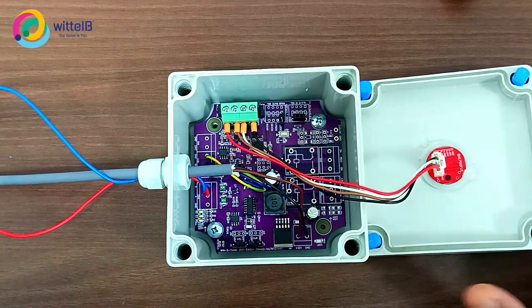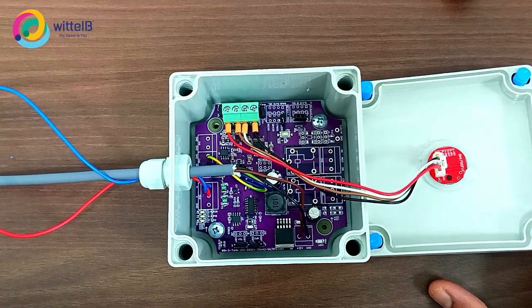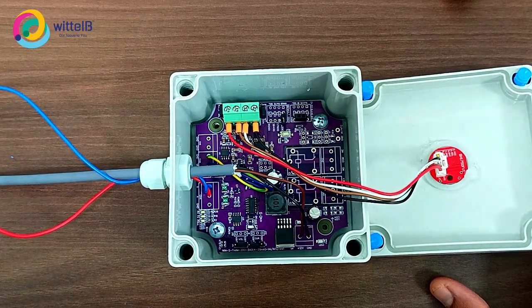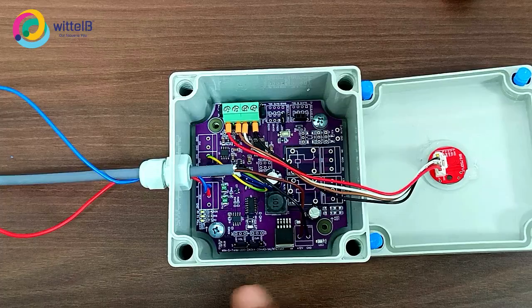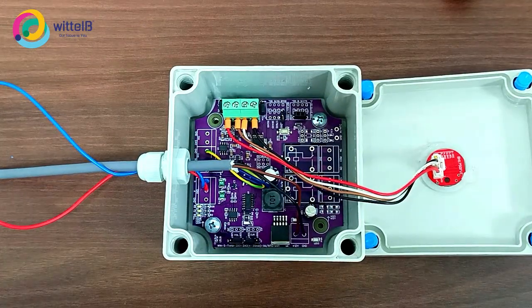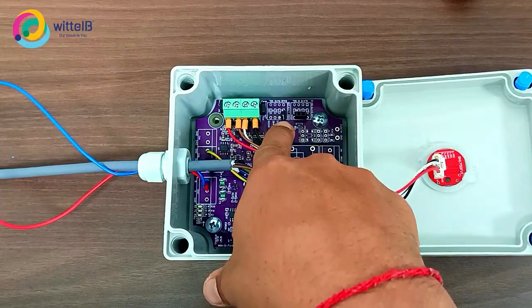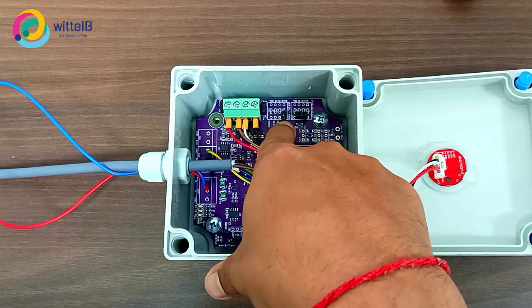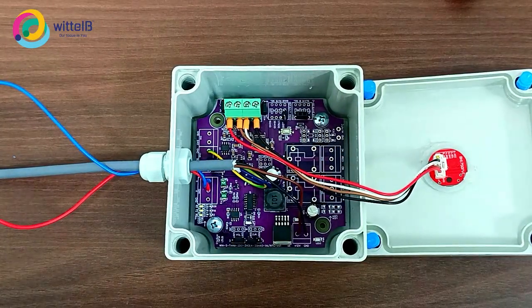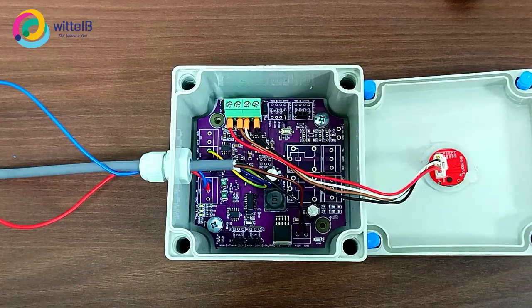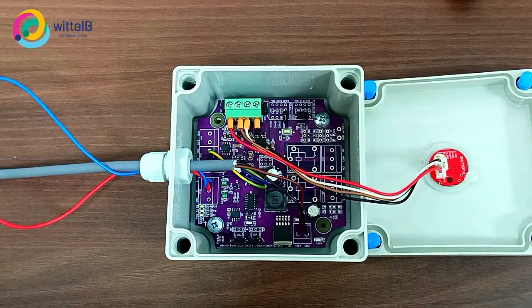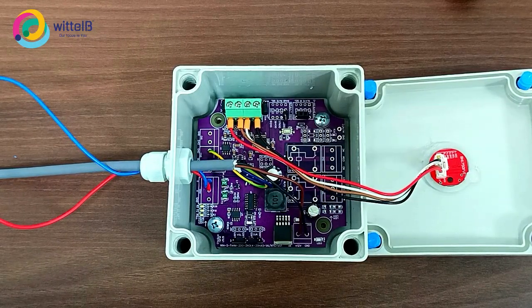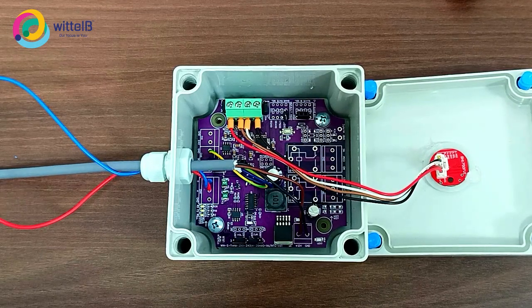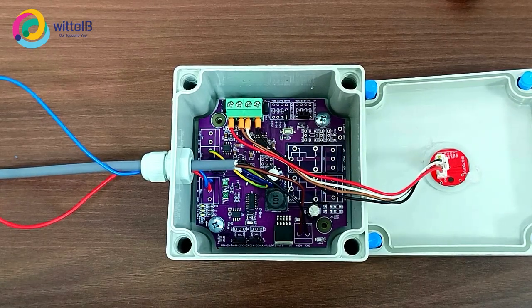In this Lux sensor we have two outputs: the analog output, which provides 0 to 10 volt, and the RS485 output, where the user can calibrate the Lux sensor. Here I have the jumper part. This jumper is used for setting the baud rate and the slave ID for the Lux sensor. The user can set their own slave ID and baud rate through RS485, where we are using Modbus.